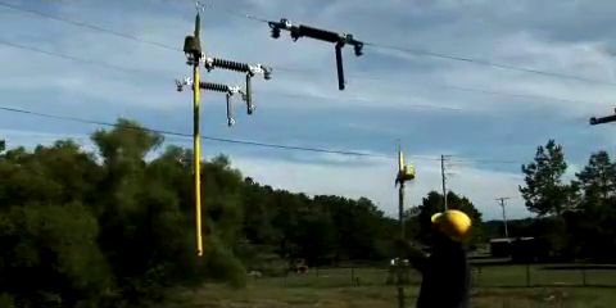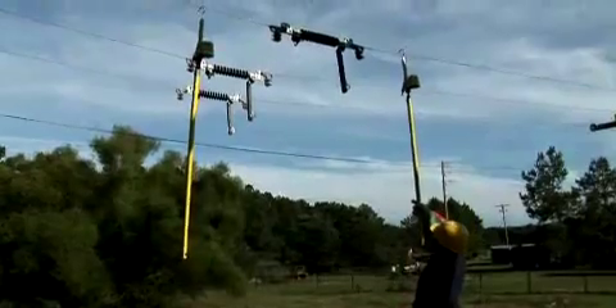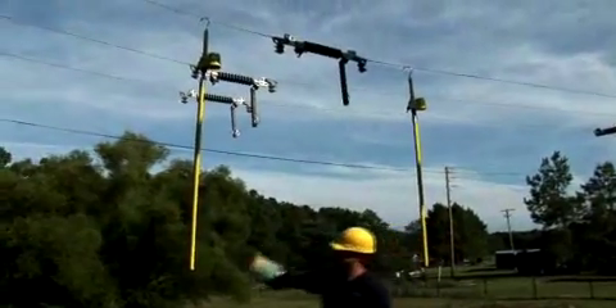Okay, I'm now going to put the reference probe up and note the reading. I'm reading 16,000 volts with a red light, and that's telling me that I'm out of phase.